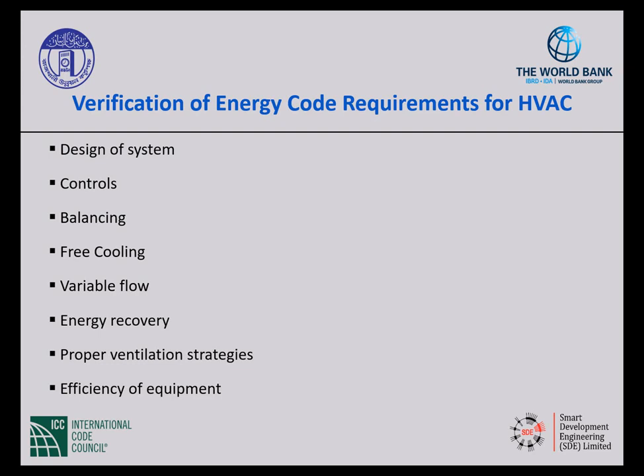Proper ventilation strategies. Are they doing mechanical ventilation? Are they doing natural ventilation? Do they have those flow rates? Do they have healthy air moving through there? Did they hook up those fans to the ceiling or the walls if they were supposed to in those certain spaces? And do they have their backdraft dampers on so that when the exhaust is not exhausting, it's closing and not letting air back in the building? Making sure that we have all of this is so hugely important.